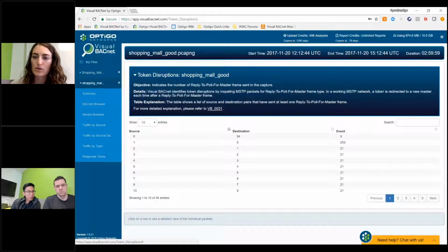Okay. So it's a BACnet network of a shopping mall. It has 59 Schneider BACnet PLCs and 1 automation server. The main problem is that the network suddenly goes down for no reason and then comes back by itself. It seems like when the network goes down, there are a lot of malformed packets spamming the network for no necessary reason. And so he captured on the MSTP network.